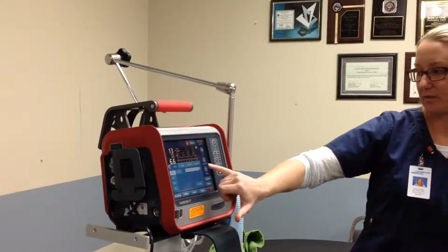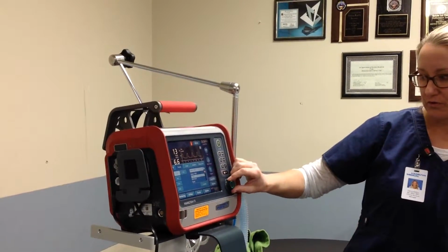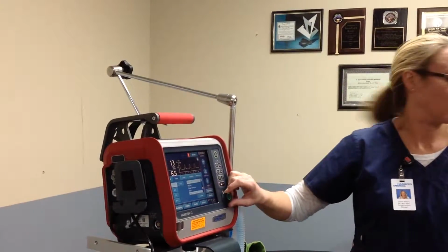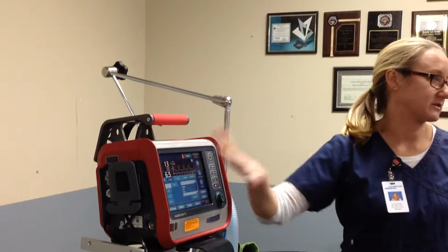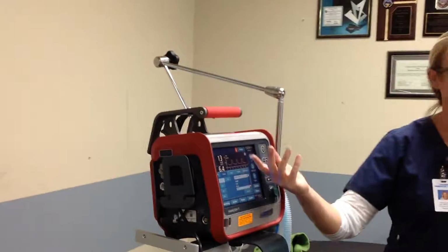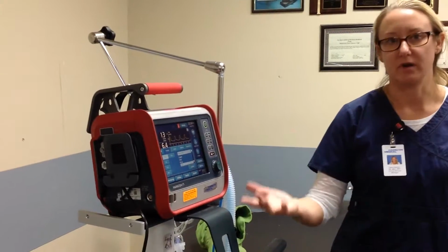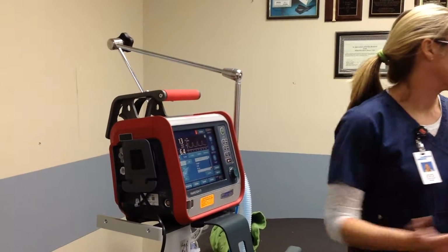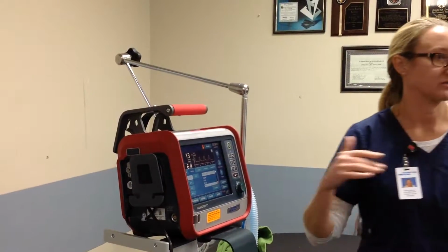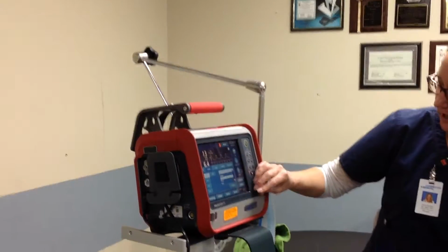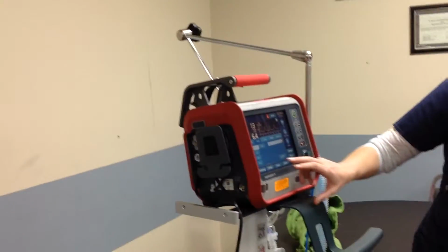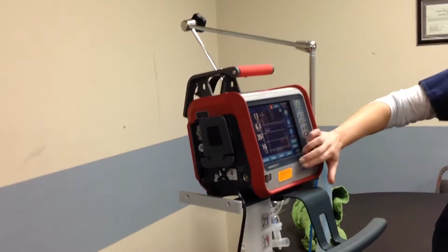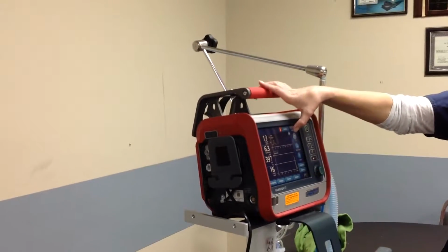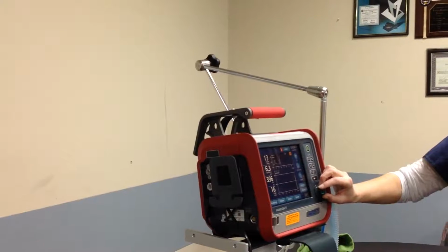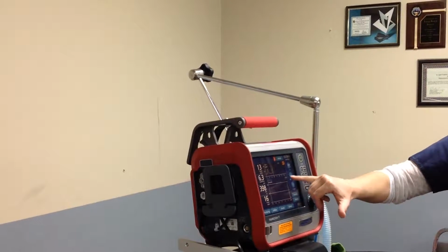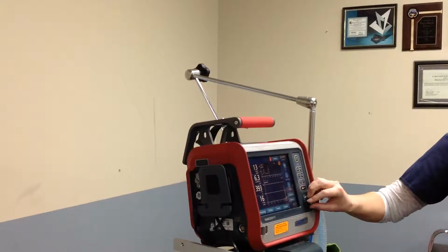So if I pull this waveform down and I scroll through, all of this data is being trended at all times. And it can trend it for as long as the patient's been on the ventilator, up to 72 hours. So if you've had a patient on the ventilator for 12 hours and you're concerned that they are going into ARDS or something like that, then you can look at static compliance over 12 hours, confirm it, and you're going to get a trending bar. It doesn't really mean anything unless you push this button here, and now as I scroll through, it's telling me at every minute within those 12 hours what that static compliance was from minute to minute.